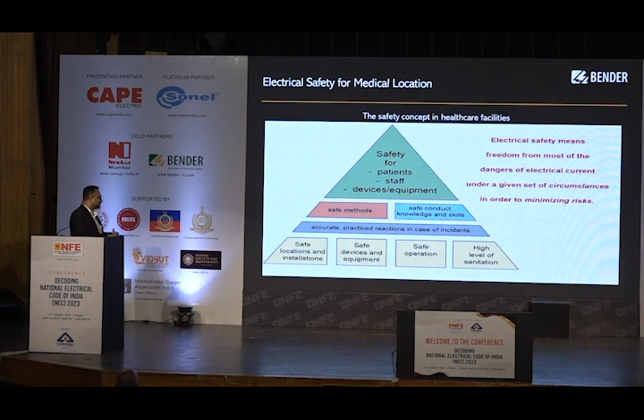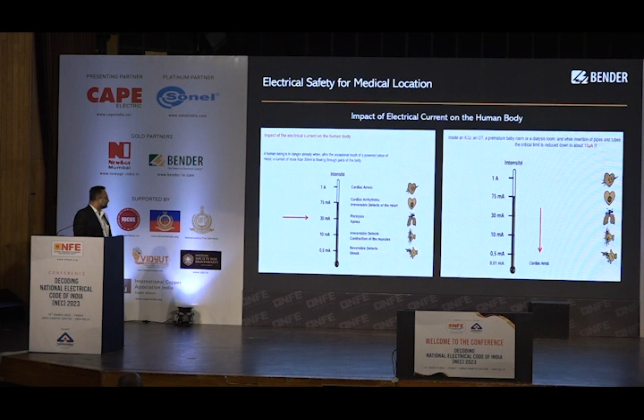A human being can tolerate 30 milliamperes for a very short time, whereas for a patient, 0.01 milliampere — that is, 10 microamperes — can be fatal when the body is open on the table. This is the basic difference, so you can understand that a normal RCD of 30 milliamperes is not suitable for OT and ICU during operations.